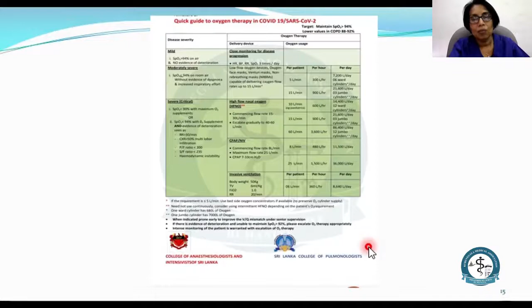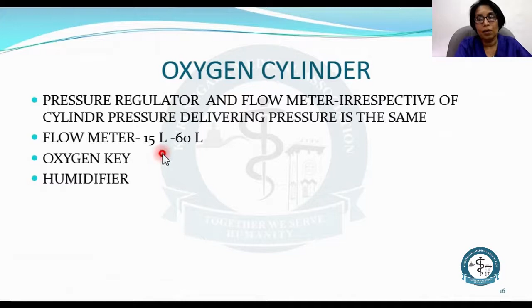Oxygen cylinder. When an oxygen cylinder is concerned, there is a pressure regulator and flow meter, and irrespective of the cylinder pressure, the delivered pressure at the outlet is the same. It's just above the atmospheric pressure. The flow meter of the cylinder can range from 15 liters to 60. The oxygen key is a very important thing when oxygen delivery is concerned. If you lose the oxygen cylinder key, you may not be able to get oxygen, and this can jeopardize somebody's life. And humidification is important because oxygen is stored under dry conditions.